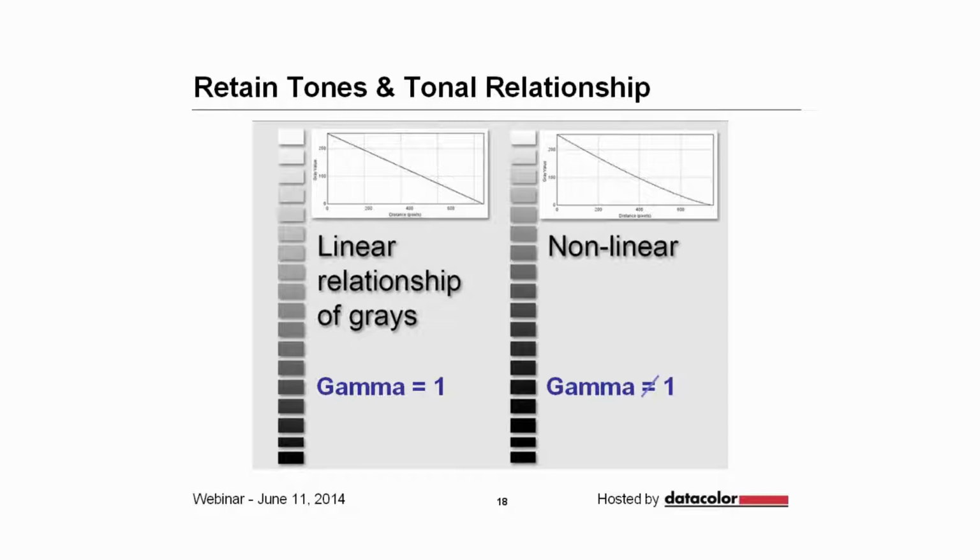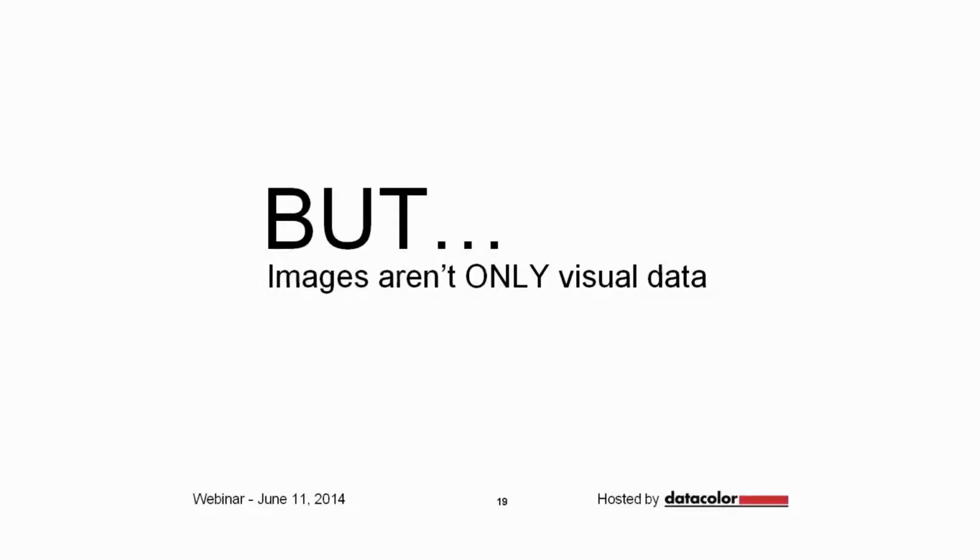or confocal or whatever the instrument is, and all of a sudden it's on something called enhance or something called contrast, and you have no idea whether or not that's changing the gamma. It's a surprise to me, and actually it's stunning to me that I could go into labs and see this. It's really important, at least for your acquired image, to have a linear relationship of tones, especially when you're saying something's brighter or darker than something else.